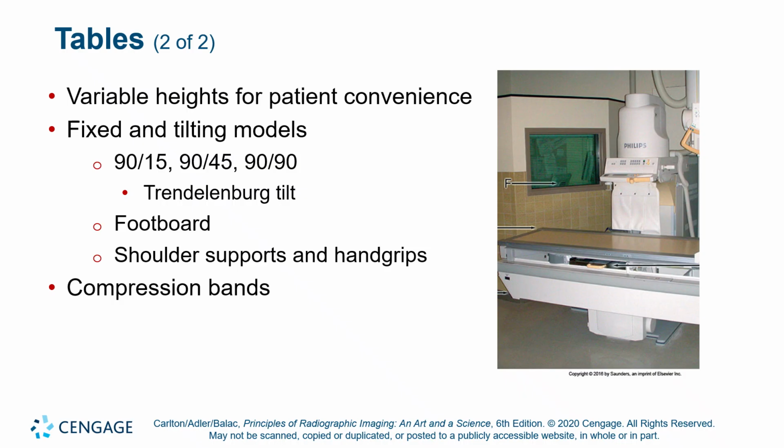Footboards are usually an attached piece that lock into the table surface by basically spring-loaded buttons, so to speak, or pegs. Make sure that your footboard is securely attached before you have your patient go for a carnival ride and experience the 90-degree tip. Okay.